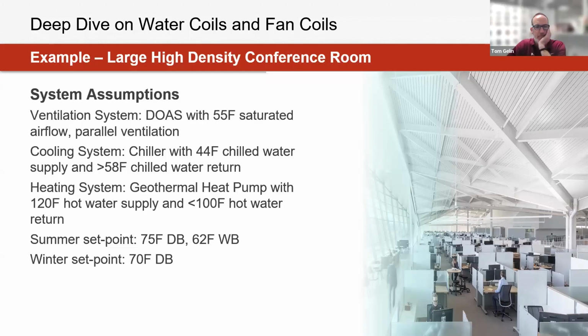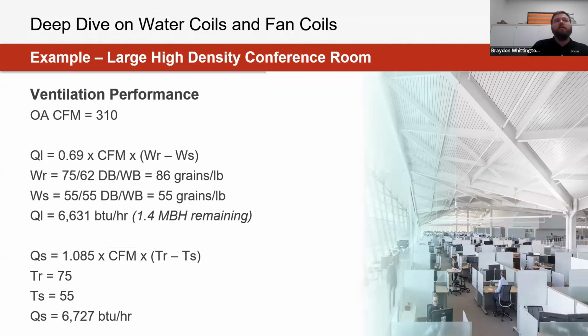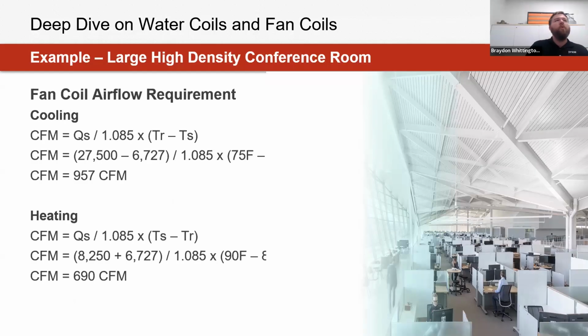So with all those assumptions in play for both the space itself, what we're targeting, and then also what our system looks like, one of our first steps is going to be determining our ventilation performance for this conditioned space. So determining both our latent as well as our sensible loads based off of our outdoor air ventilation of 310 CFM, based off of the number of occupants we would see within that 800 square foot space. And don't worry, I'll send this slide to everyone, so everyone can run through this example on their end, if you ever want to use this as a reference point.